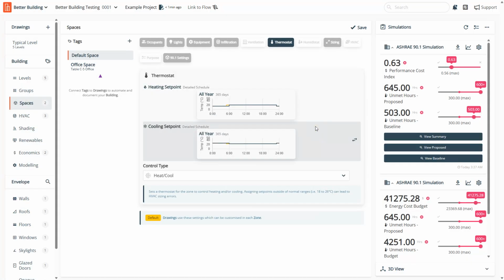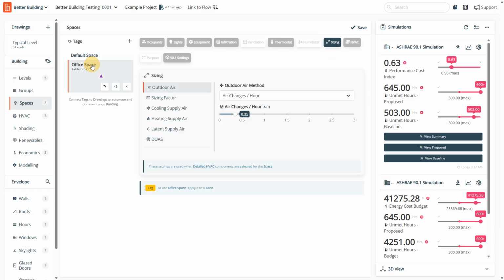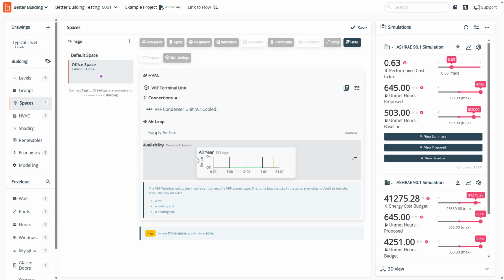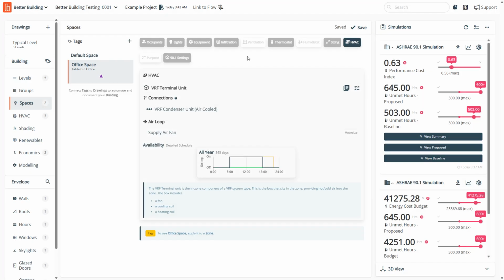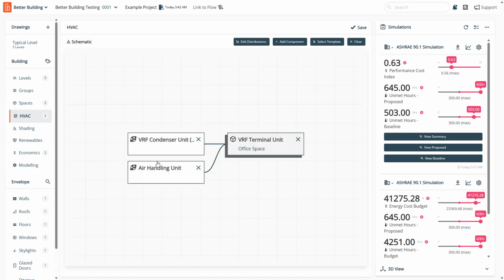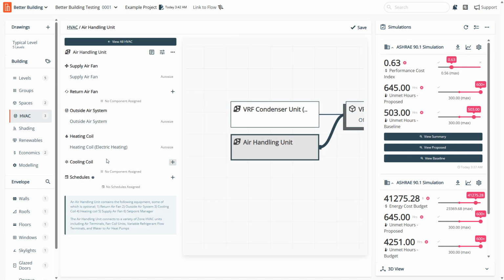Let's look at the Sunday. We have the backstops. Looks like that's reaching up there. So it's probably the fact that we might be just dumping too much air into this space. There is our VRF now added on. Feels like it's a question of just dumping too much air. So going back to our HVAC system here, effectively, yeah, we've got no cooling coil on the air, all that warm air that's coming in.